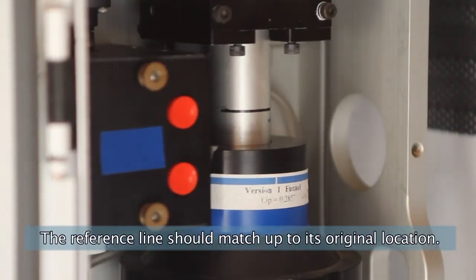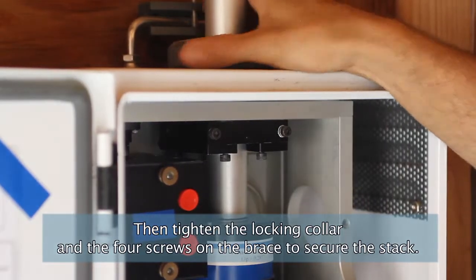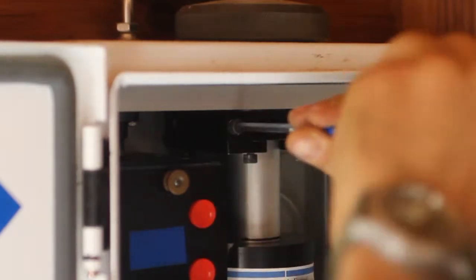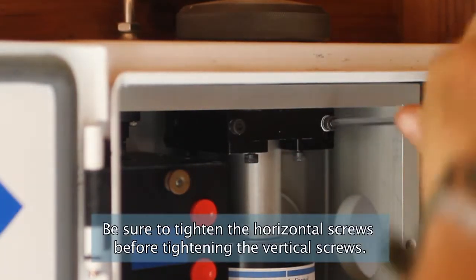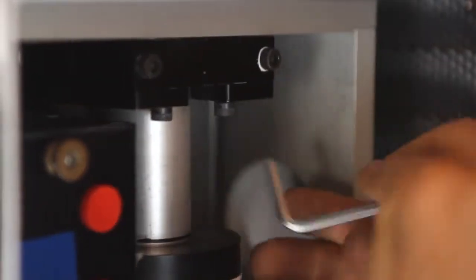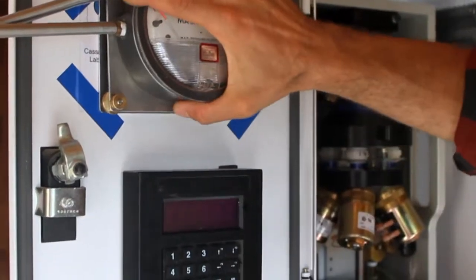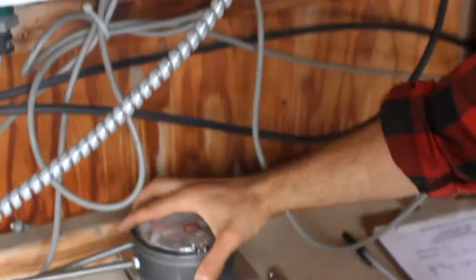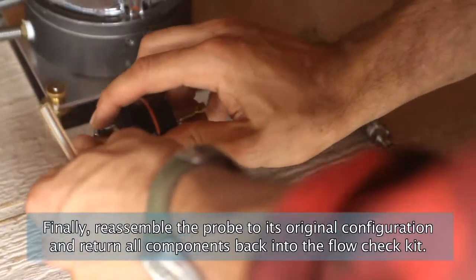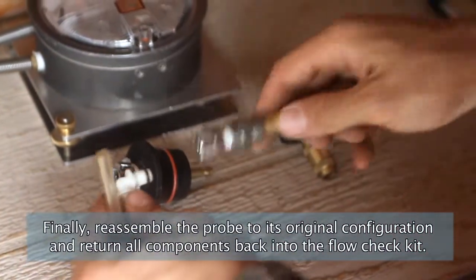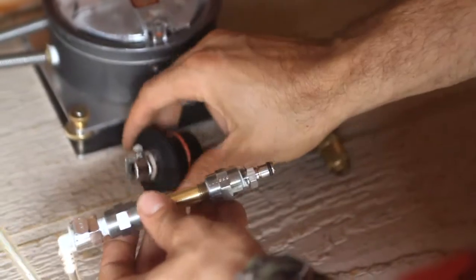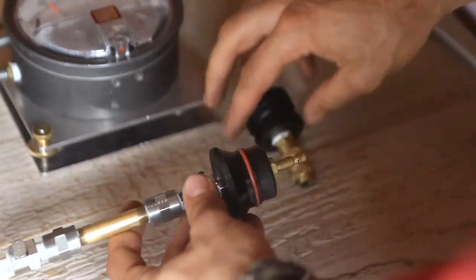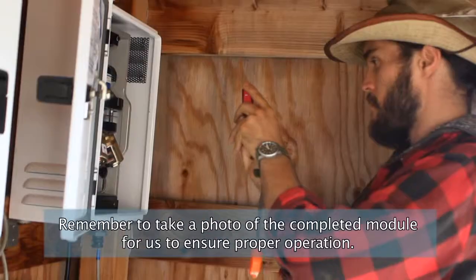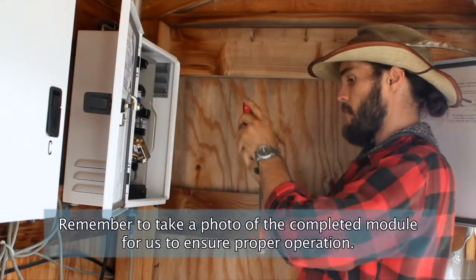The reference line should match up to its original location. Then tighten the locking collar and the 4 screws on the brace to secure the stack. Be sure to tighten the horizontal screws before tightening the vertical screws. Finally, reassemble the probe to its original configuration and return all components back into the flow check kit. Remember to take a photo of the completed module for us to ensure proper operation.